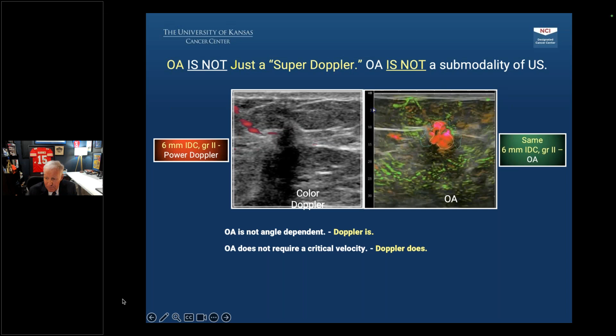Doppler also requires a critical velocity. If blood is too slow, it can't see it. For instance, you can't see blood flow in a placental lake with Doppler. OA does not require a critical velocity. The big difference is in the contrast ratio. This means that OA can tolerate a lot of volume averaging where Doppler can't.